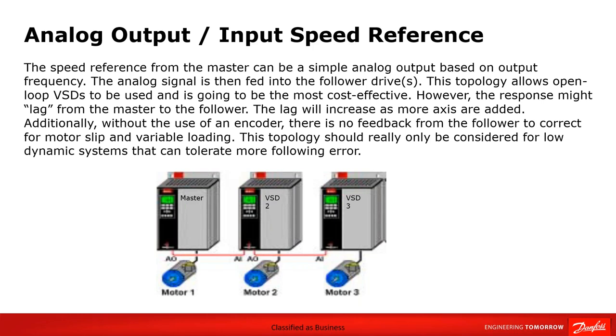So let's look at the analog output input speed reference, which I've made mention of. The speed reference from the master can usually be just a simple analog output based on output frequency. This analog signal is then fed down into what we call the follower drives. And this methodology allows what we call open loop variable speed drives to be used, and it will be the most cost effective.